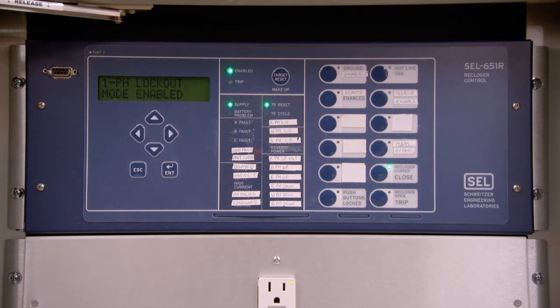You'll be able to get an instantaneous current reading from that recloser itself. You'll be able to tell whether the controller is in a bypass state or it is in an open state. In the field, and when installing the leads on the main line, you'll be looking for a zero current reference. On the display screen, you can see that you have a continuous current reading and it is a 0, so you have no current flow.